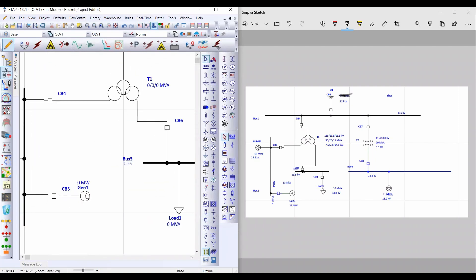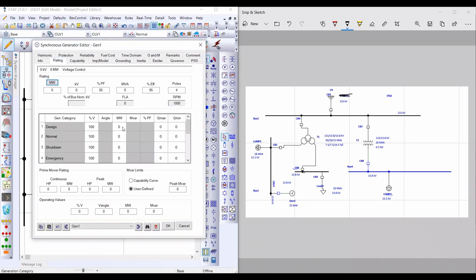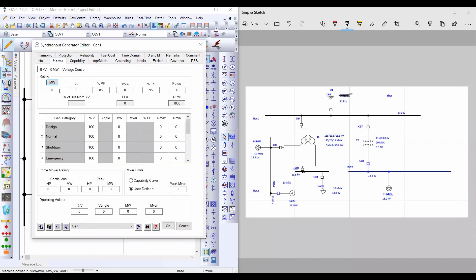The second step — I will insert data for the generator. The name of this generator is 'Generator 3', and the operation mode is Voltage Control. Select Voltage Control to control the voltage; this also provides fixed megawatt output. From Rating, the megawatt rating of this generator is 25 MW and the rated kilovolt is 13.8 kV.